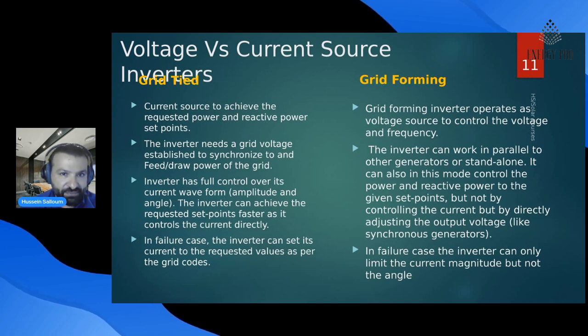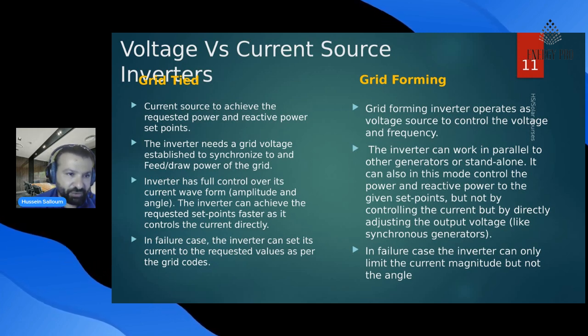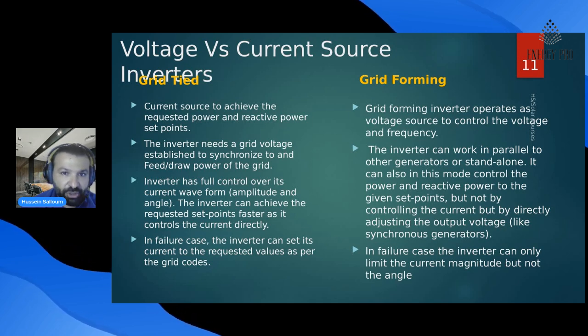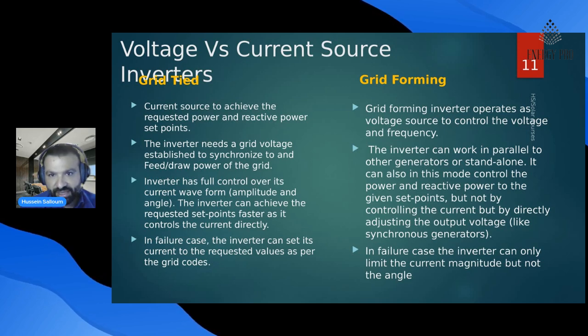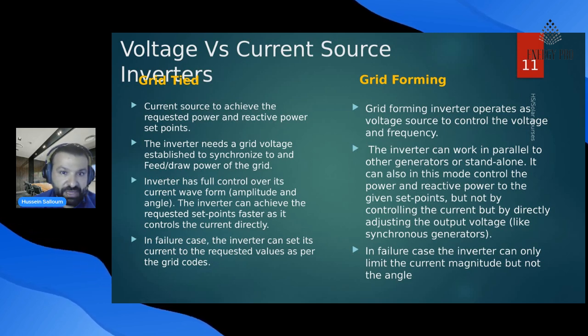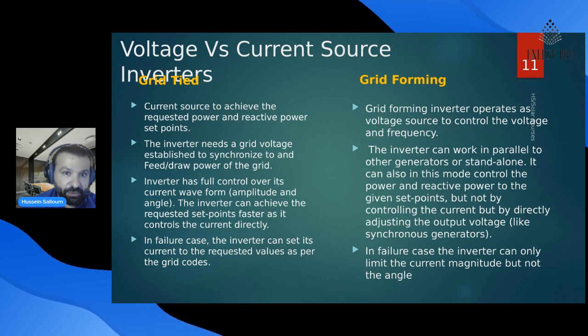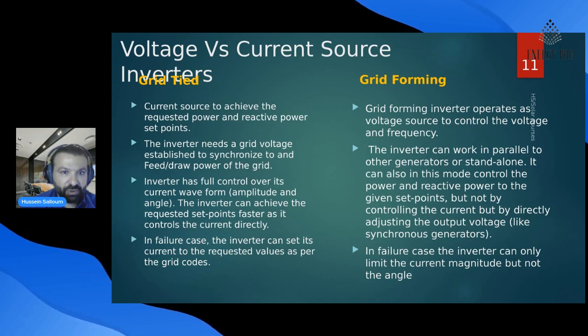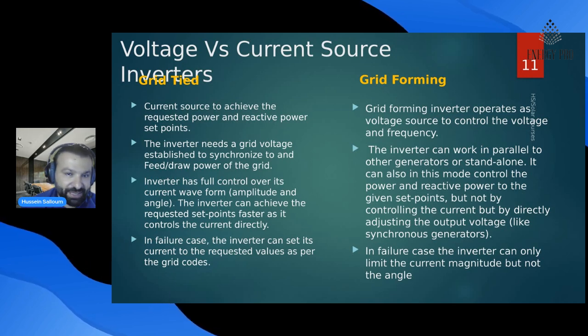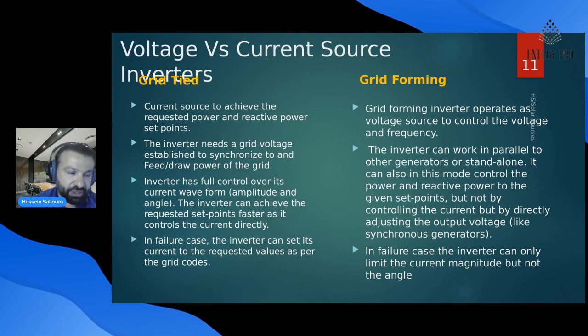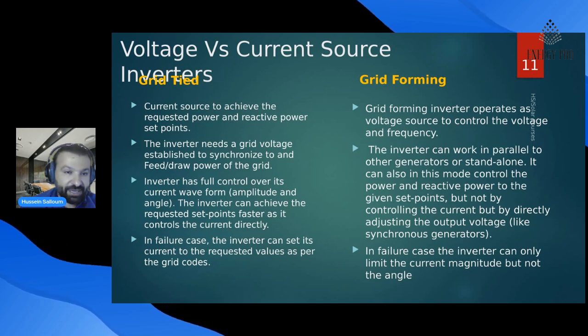On the other hand, there's the grid forming inverter. The grid forming inverter operates as a voltage source basically and controls the voltage and the frequency of the system. So this inverter will work in parallel with the other generator or the battery or a standalone system, and it can also be used in the mode control of the active and the reactive power to given set points. So it will not only be controlling the current, it will also be adjusting its voltage to suit the system voltage. So this grid forming inverter can be used as a voltage source. However, this inverter will use more PV modules to be able to give the flexibility for this kind of inverter to maintain the voltage levels.